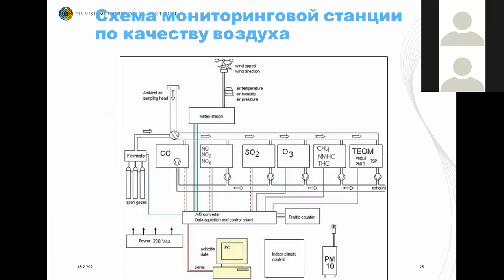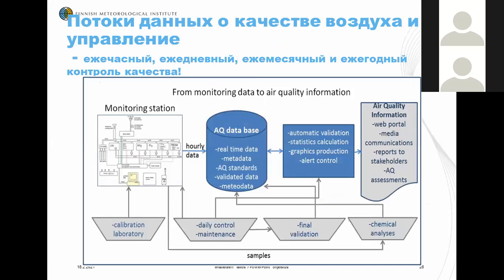Okay, this is the same picture I already illustrated yesterday. So this is the monitoring site. Let's go next one. And this is the same picture I illustrated yesterday also, of how the quality is then transferred to the measurement site. So in this picture the National Reference Laboratory is here under the monitoring station. So the calibration laboratory, the National Reference Laboratory, is the entity that gives the traceability to each of the monitoring sites through the field calibrator. That's the way to do it.